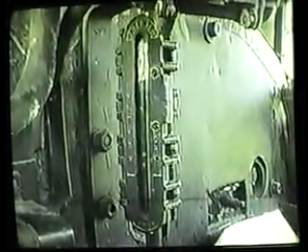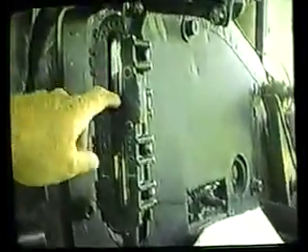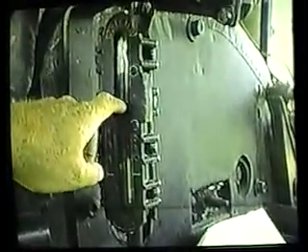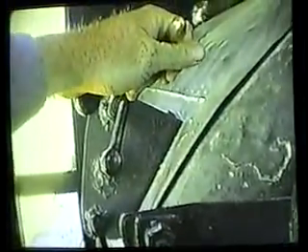Remember to keep an eye on the water glass. Make sure that you have a sufficient amount of water. Check it with the use of the try cocks. If you need to put water in the boiler, open up the injectors. Feed just as much water as you need as it's making steam.